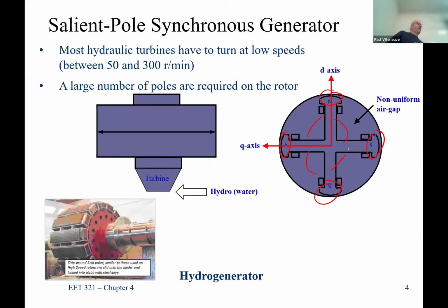Most of the time you want slow speed, because you don't want to run this at 3,600 RPM, although you can - you just have to build it more robust. This type typically runs between 50 and 300 RPM, or generally 1,800 RPM and less. So if I tell you a machine runs at 3,600 RPM, it's almost guaranteed to be a round rotor.